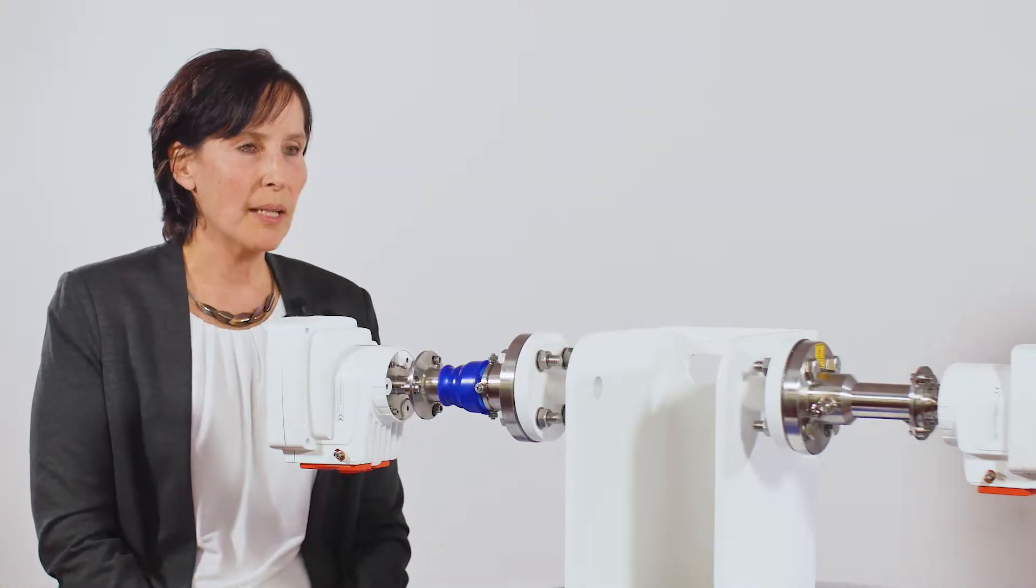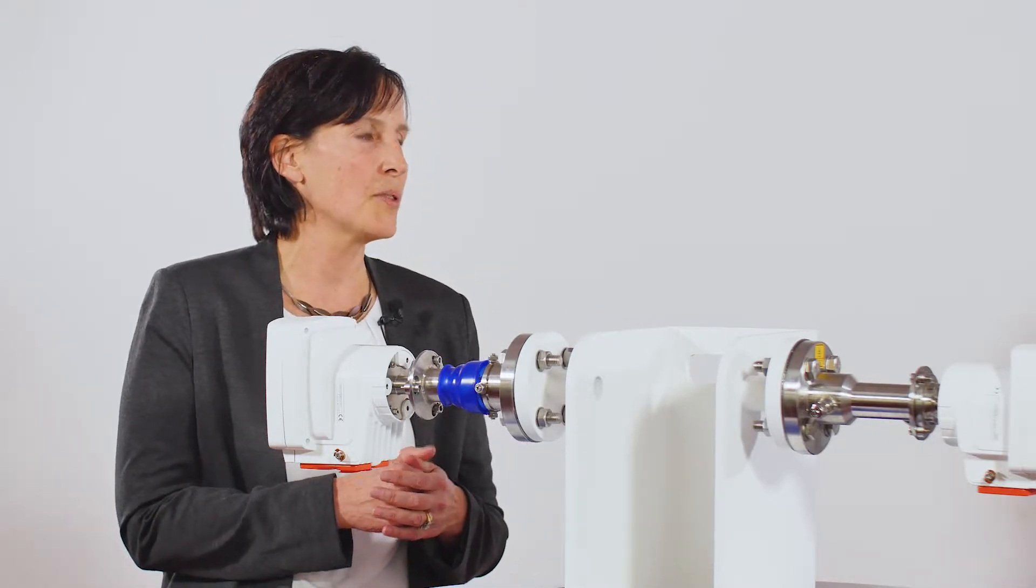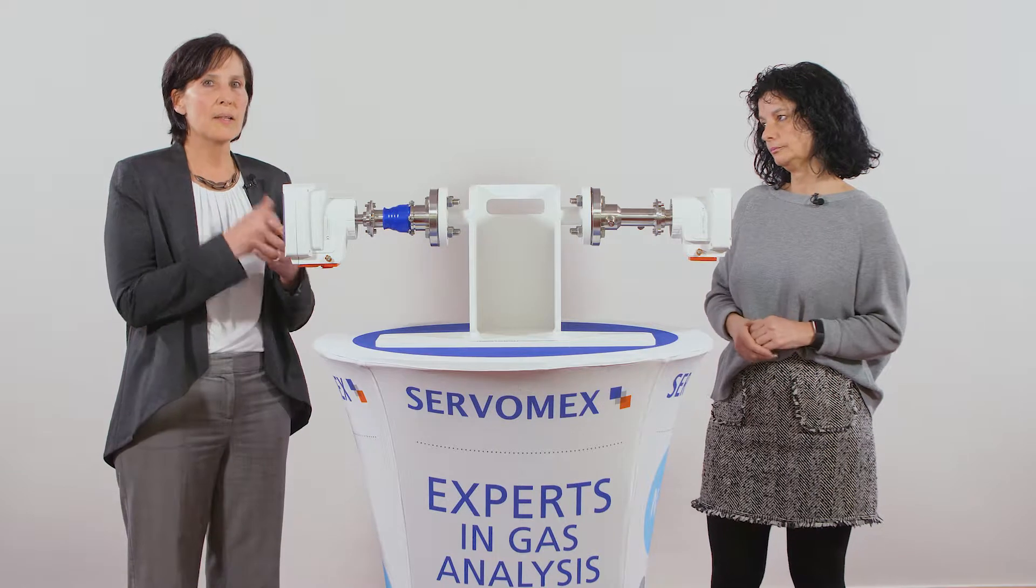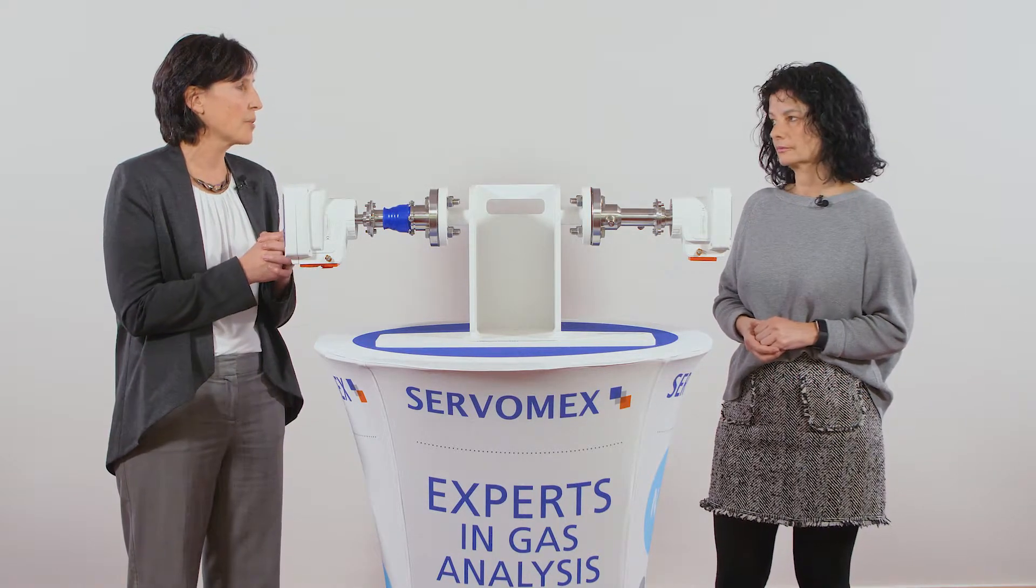So one of the things is that now that we're adding ammonia, if you add too much ammonia, one of the problems that you're going to have is you get particulate buildup. Things start to clog, things start to corrode, because this particulate is actually very acidic.